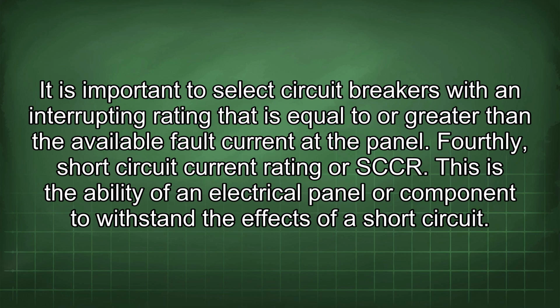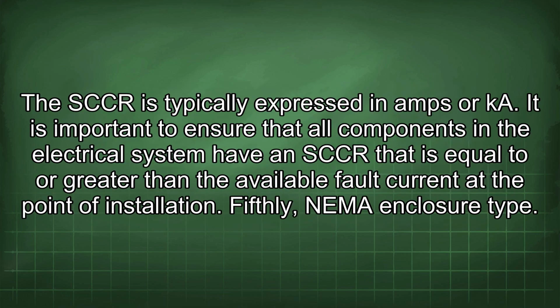Fourthly, short circuit current rating, or SCCR. This is the ability of an electrical panel or component to withstand the effects of a short circuit. The SCCR is typically expressed in amps or kA. It is important to ensure that all components in the electrical system have an SCCR that is equal to or greater than the available fault current at the point of installation.